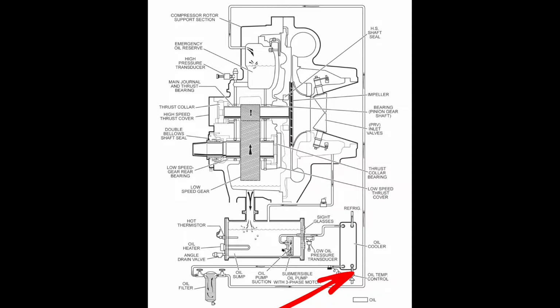And if we have subcooling and we have good liquid level, which on these machines, 1/3 to 1/2 sight glass is kind of like a starting point, and then you can tune it in from there based off of your subcooler plate level. So that's one of the things we have to look at. It's a whole nother in-depth conversation. Point is, we need to make sure we're feeding enough liquid or a subcooled liquid to the oil cooler metering valve, and that this valve is actually functioning properly.